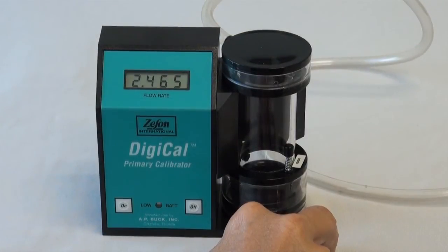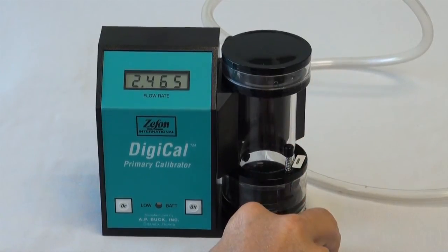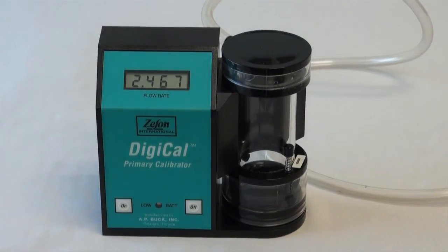Operate the primary calibrator as directed by the manufacturer's instructions. Obtain at least six readings which are very close to one another. In this video, we have an average reading of 2.46 liters per minute according to the primary calibrator.